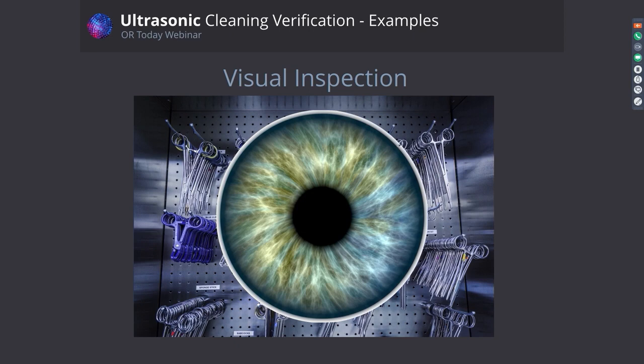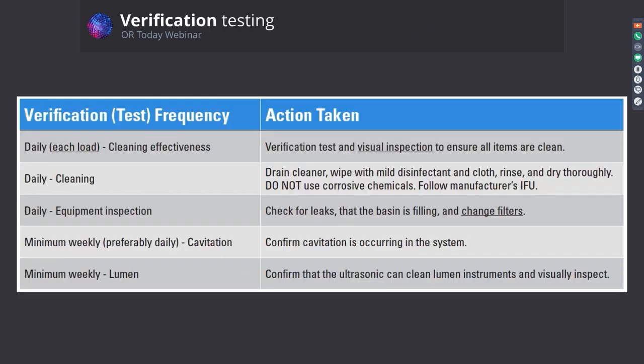In terms of verification testing, do so daily for cleaning effectiveness. Visually inspect to ensure items are clean. Clean daily: drain the cleaner, wipe with disinfectant cloth and dry, and don't use corrosive chemicals. Follow the manufacturer's IFUs for the cleaning process. For daily equipment inspection, check for leaks, make sure the basin is filling, and change your filters daily.